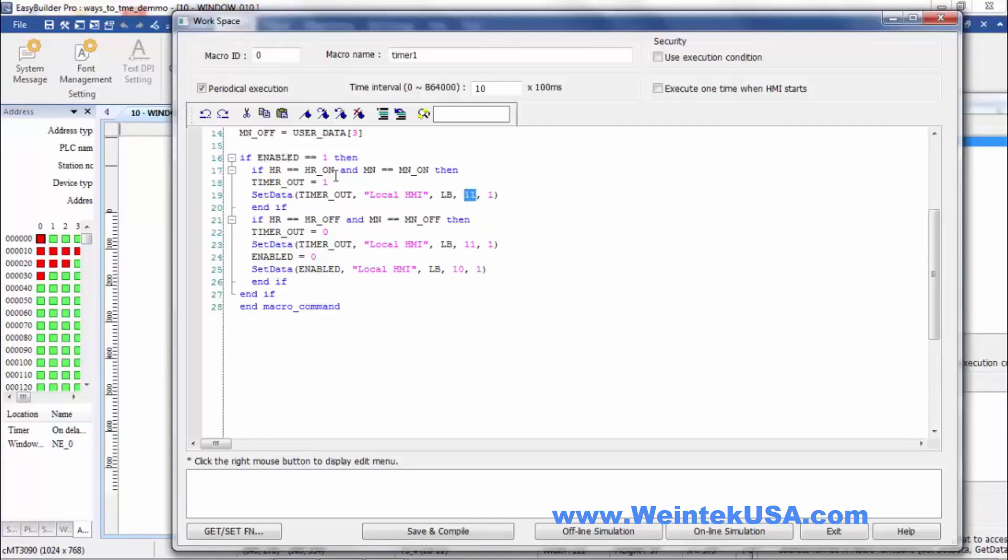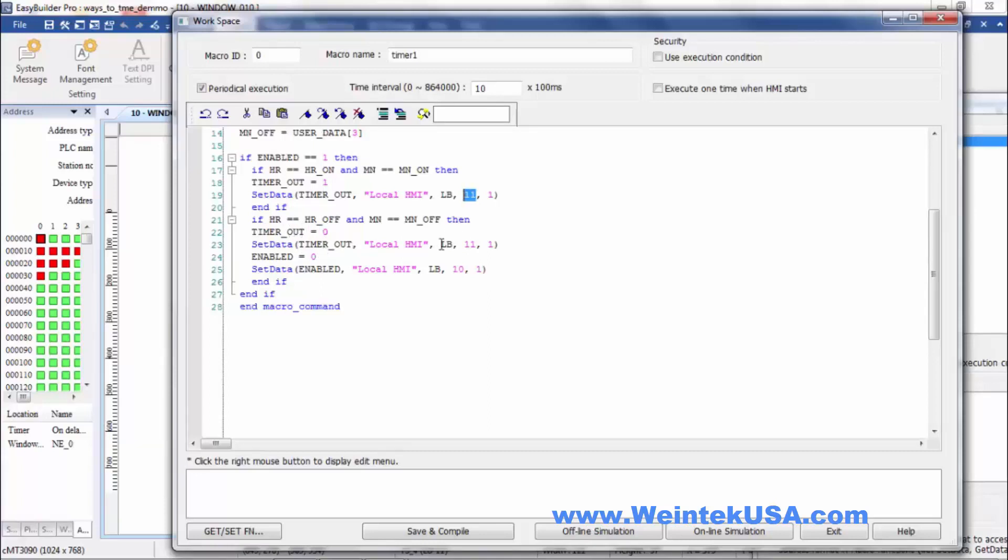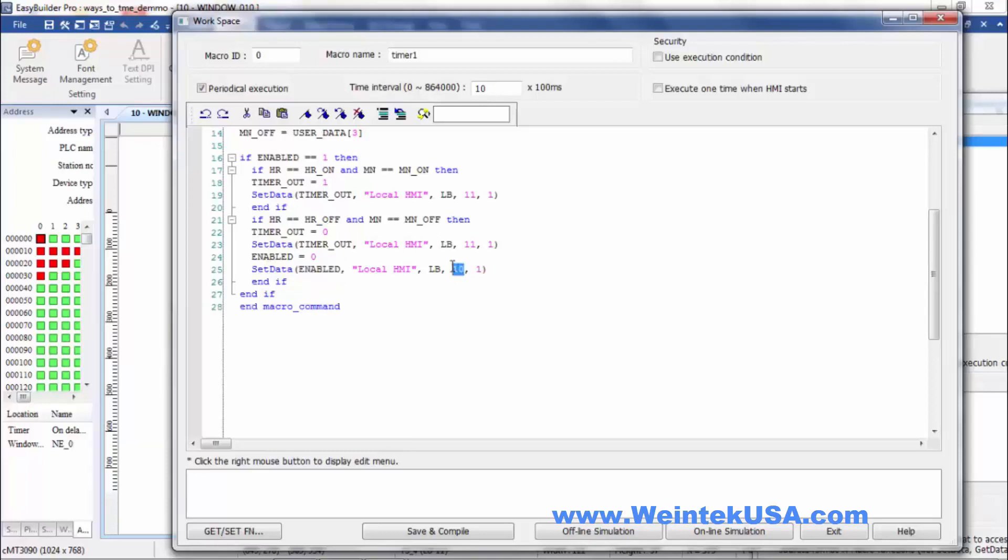Or if it's enabled and the hour equals the off hour and the minute equals the off minute, then we write a zero to our timer out object and write that value to LB11, to our output bit. And at the same time when we turn it off, we also turn off our enabled. Enabled equals zero and we write that to our enabled bit, LB10.